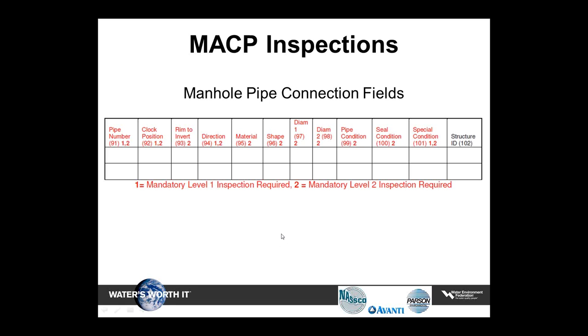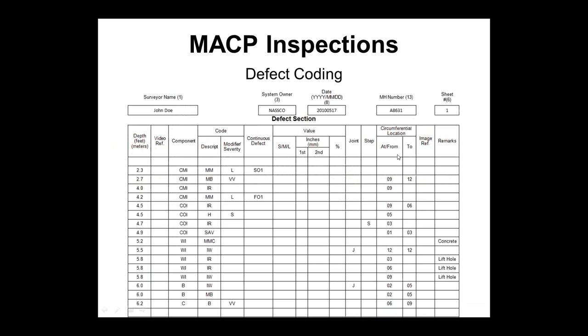The next information you may collect, especially when you get into Level 2 inspections, is information on the pipes coming into and out of the manhole — including clock position, depth or rim to invert, material of the pipe, shape, diameters, general condition, and any type of seal condition. The defect coding reuses almost all of the codes from PACP that you would see for defects within a pipeline, using the same codes for the manhole — things like infiltration runner (IR) and missing mortar — all the way from the cover down to the channel, using abbreviations for the cone, wall, and channel.